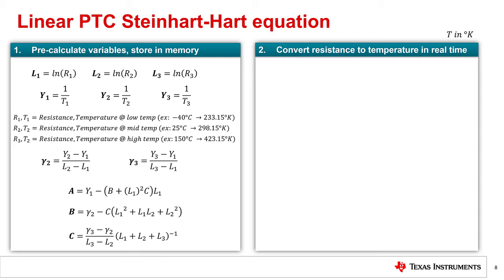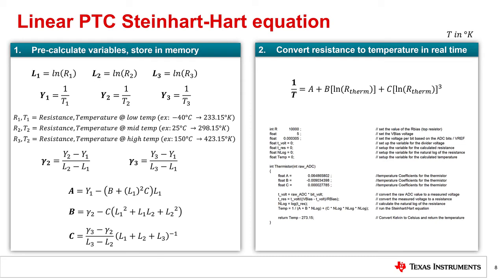During operation, one over the temperature in degrees Kelvin is equal to A plus B times the natural log of the resistance of the thermistor plus C times the natural log of the resistance of the thermistor quantity cubed. Compared to the lookup table method, there is no loop in code that you would have to design, but you still need to go through the steps of calculating the thermistor's resistance value.